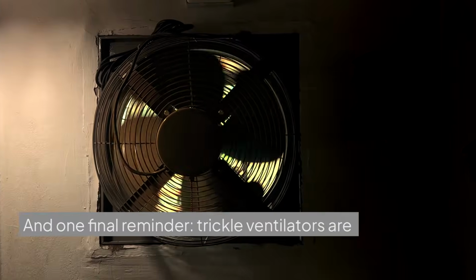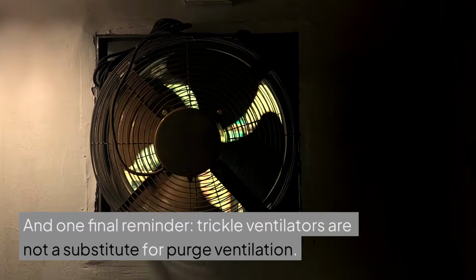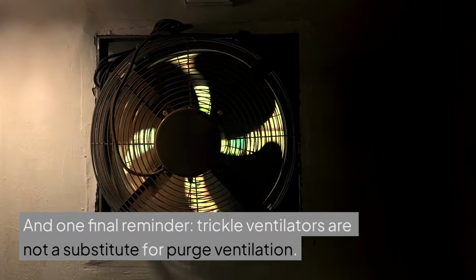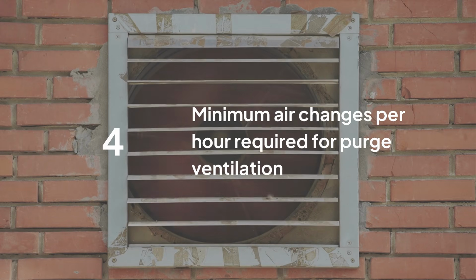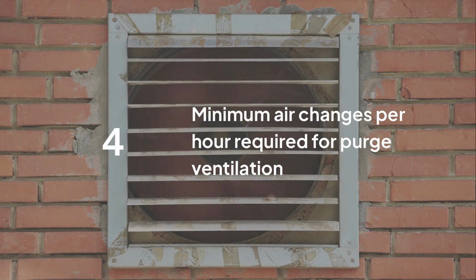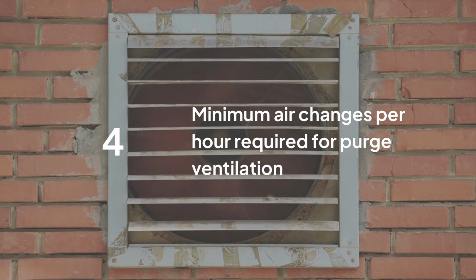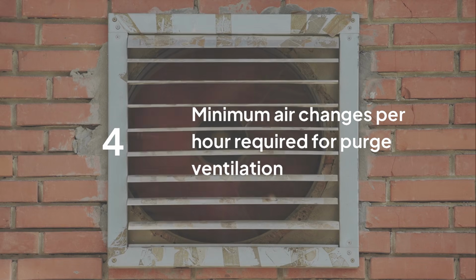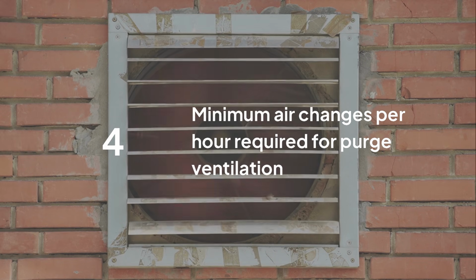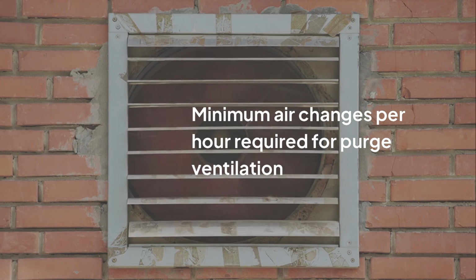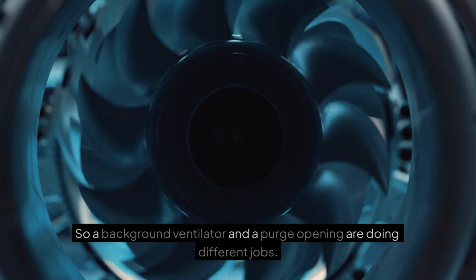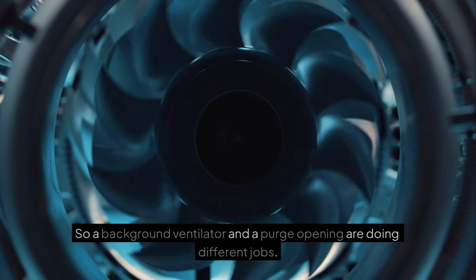And one final reminder, trickle ventilators are not a substitute for purge ventilation. Approved Document F says each habitable room should have purge ventilation capable of at least 4 air changes per hour directly to the outside, either through openings such as windows or doors, or through a mechanical extract ventilation system. So a background ventilator and a purge opening are doing different jobs.